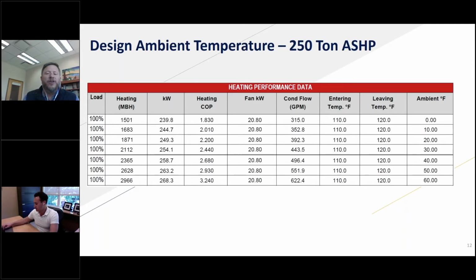Perfect. So as I talked about previously, when we talk about how an air source heat pump operates, a boiler is going to look at a return water temperature and a supply water temperature, and its input is gas, or electricity if we're using an electric boiler, and that's really going to drive what the capacity is. So it's really looking at how many BTUs you need to get that water from its return to its supply temperature. When we look at an air source heat pump, there's another factor in play, because we're not burning something or using something to make heat. We're simply moving heat.